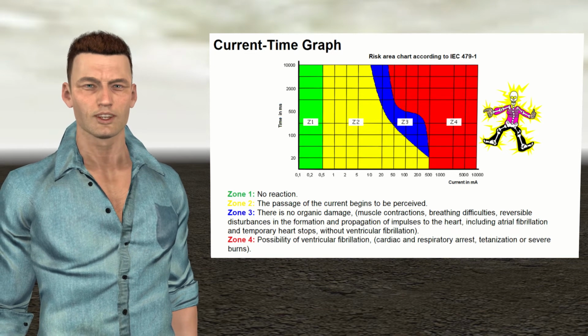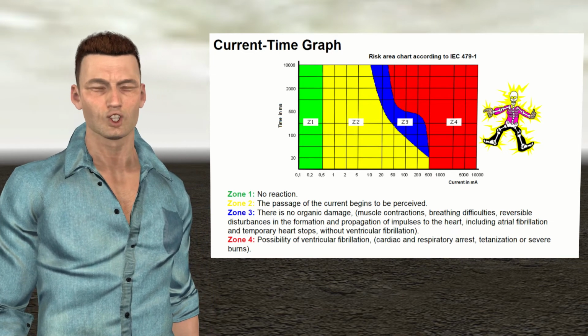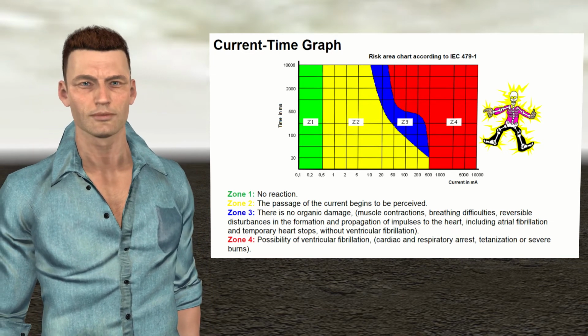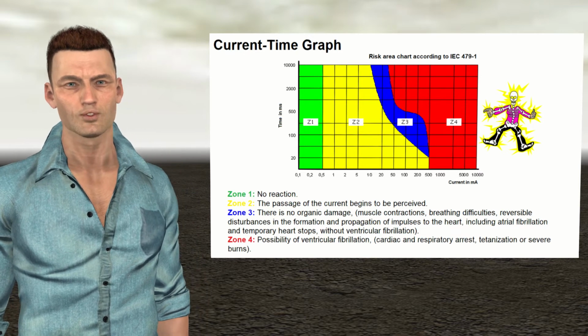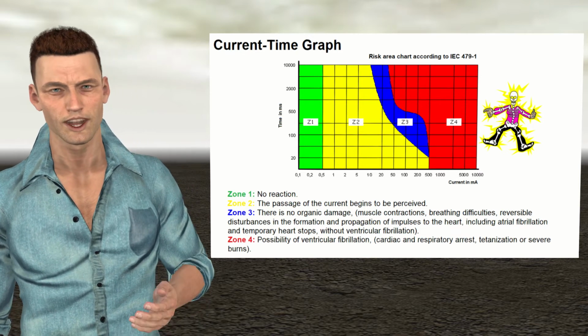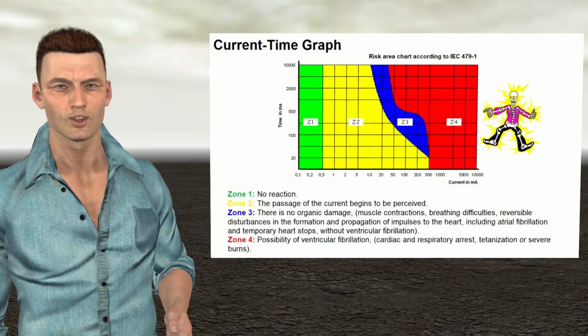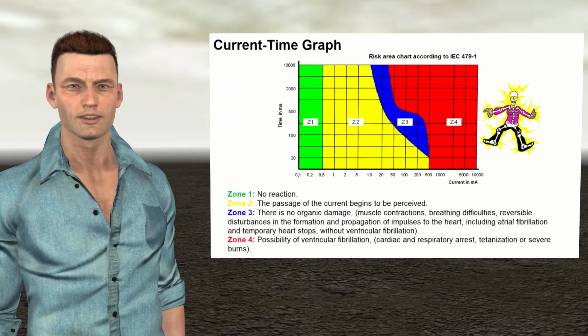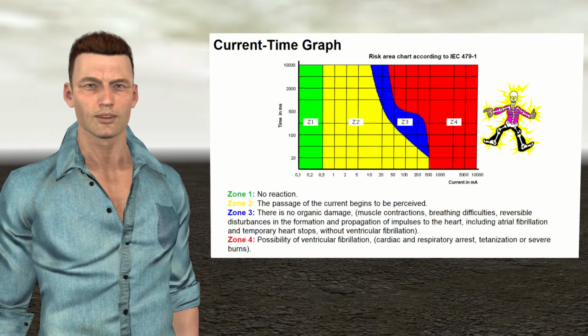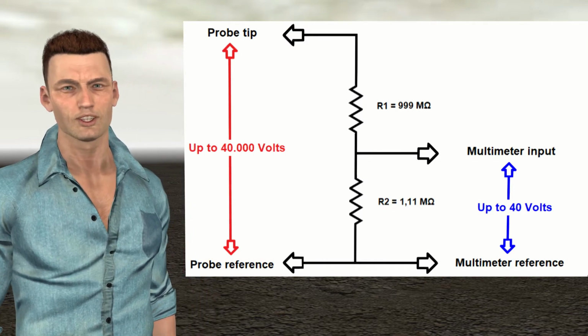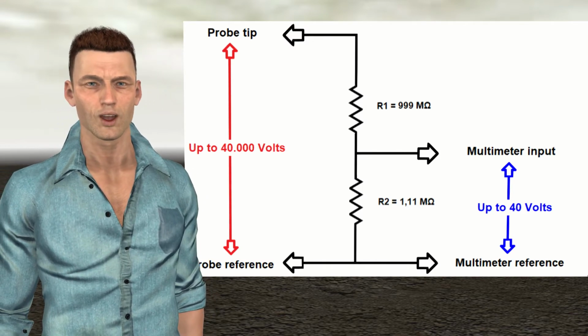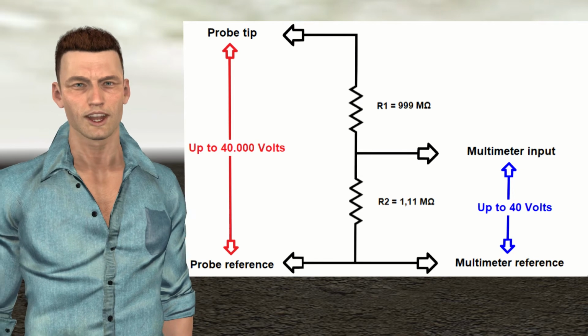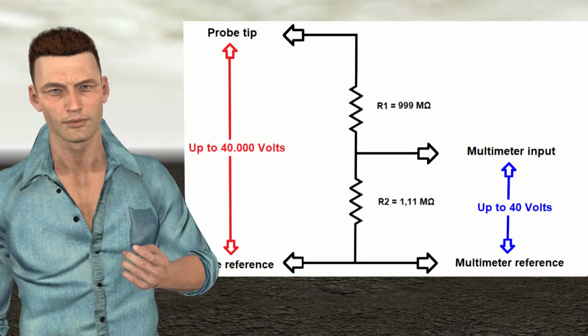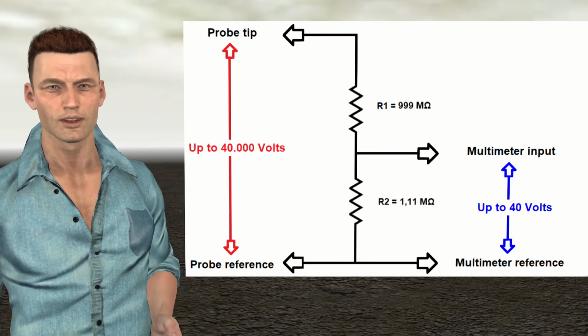If for example we consider an average value of the resistance of the human body of 1000 ohms, then a voltage of 40,000 volts would suppose a current of 40 amps, and that would definitely place us in the high risk area. As we can see in the diagram of the Fluke 80K40 probe, it is composed of two resistors, one of 999 megaohms and the other of 1.11 megaohms, which form, as in the previous examples, a voltage divider.